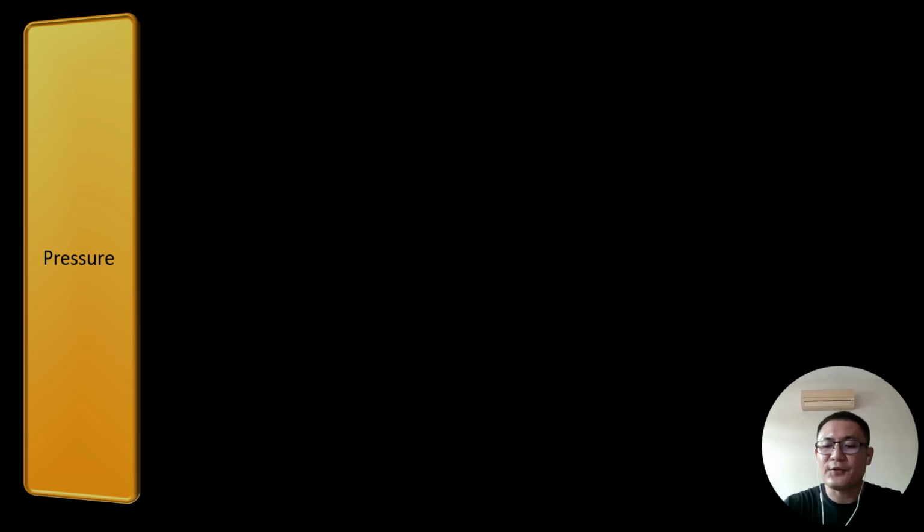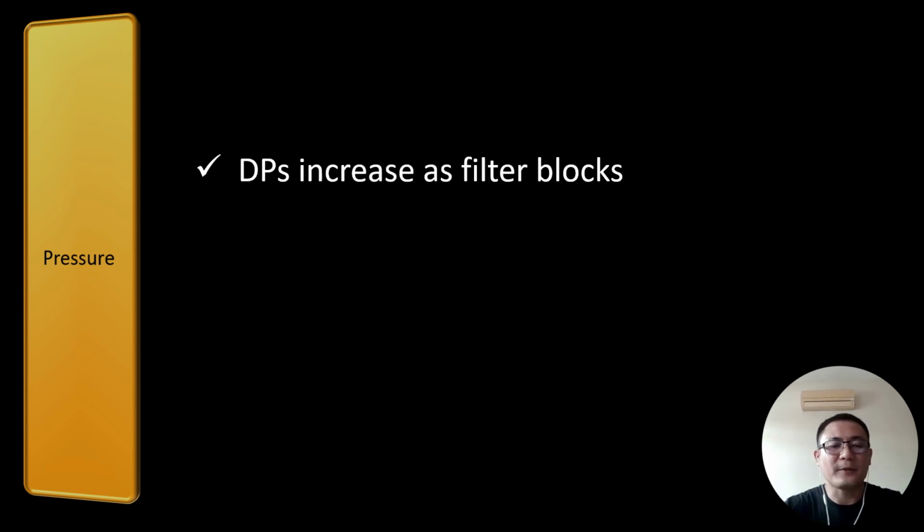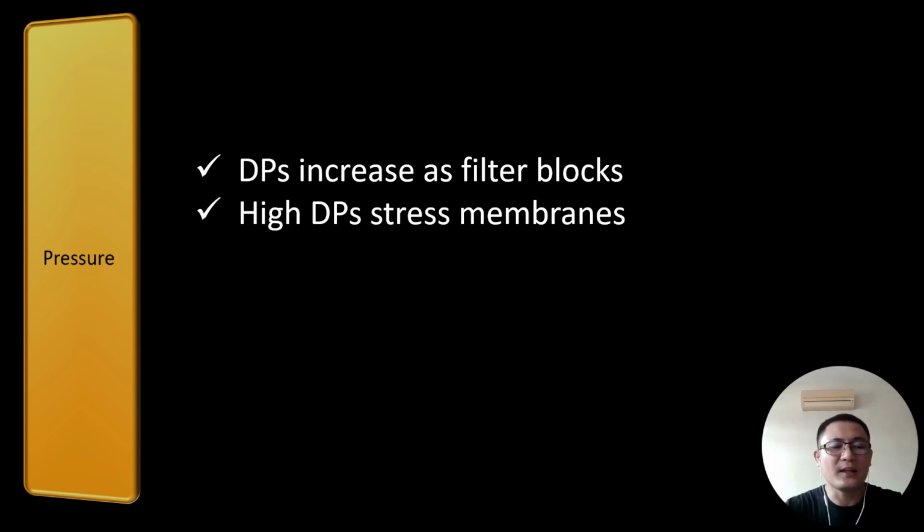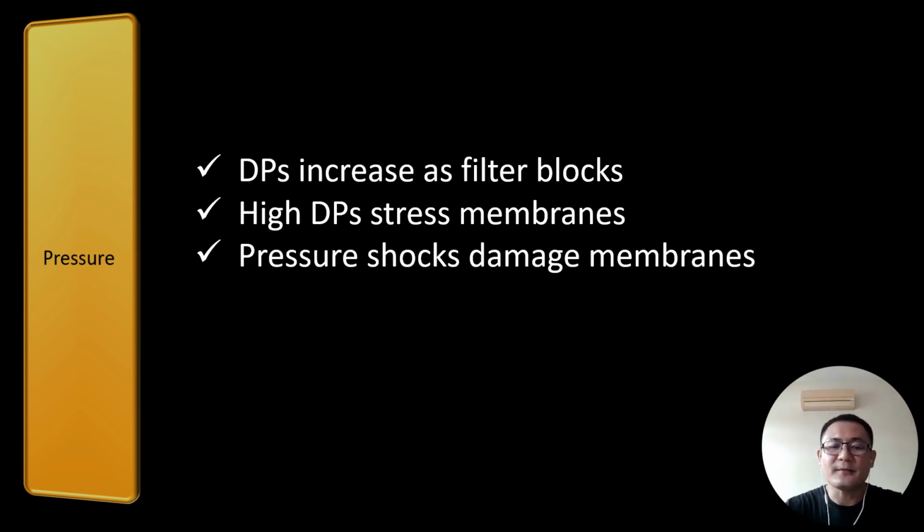Next, let's review from the point of pressure. Differential pressure across the filter will increase once the filter gets blocked. Subsequently, it will make the filter feel stretched. This pressure shock is likely to damage the filter. As we know, filters have pores.